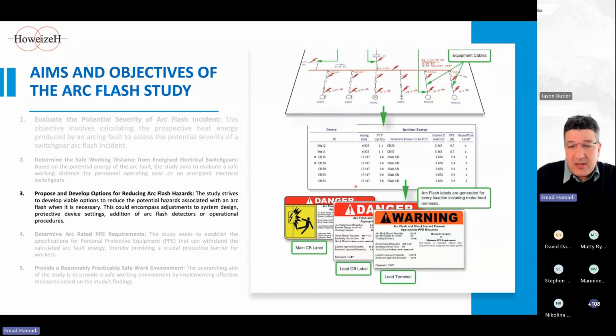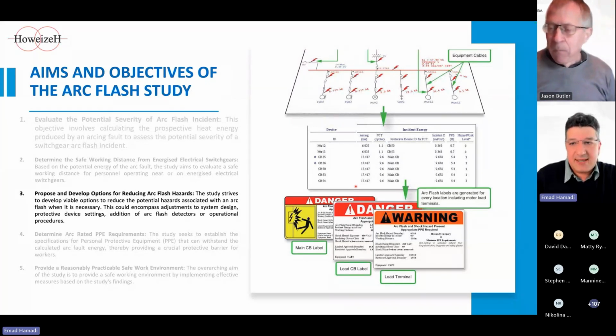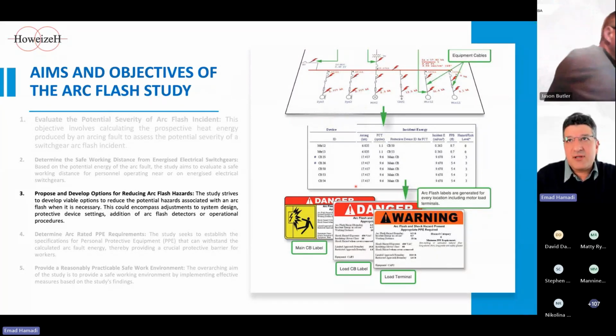Okay. One of the key objectives of the arc flash study is to propose a solution, an option, for reducing the potential hazard associated with the arc. This is, in fact, identifying and implementing different strategies to mitigate this risk in a cost-optimum way, if you like. For example, fine-tuning the protection settings. I saw a question asked by David regarding the protection setting and whether it can reduce the arc flash. Yes, it can be done. Actually, it is one of the ways of reducing the arc flash.